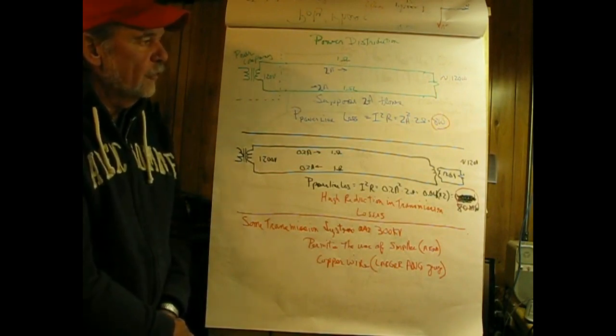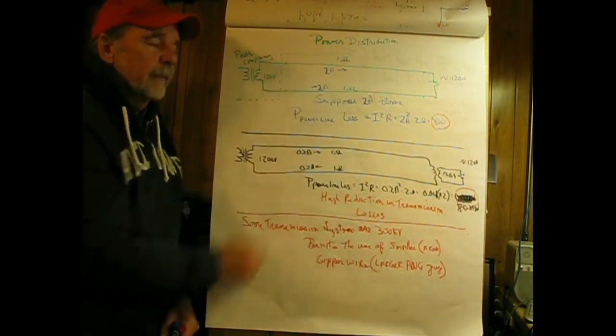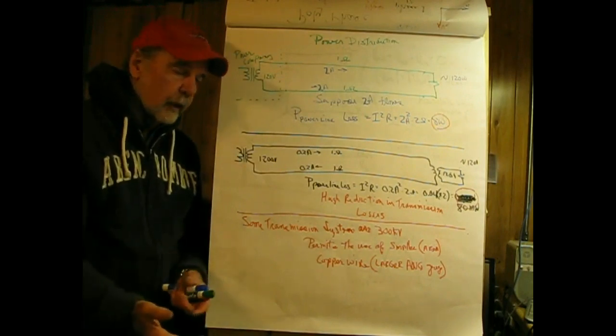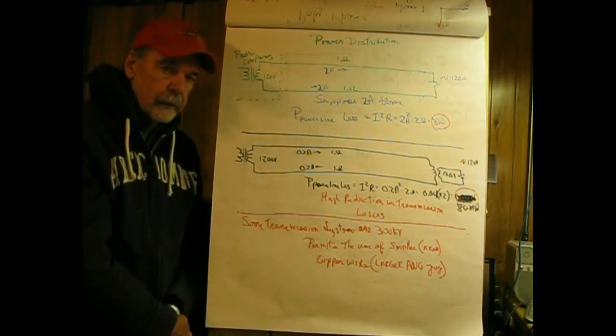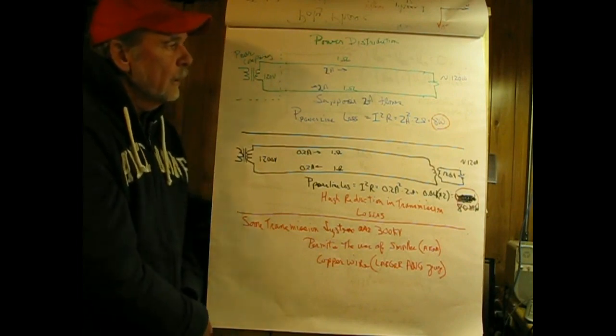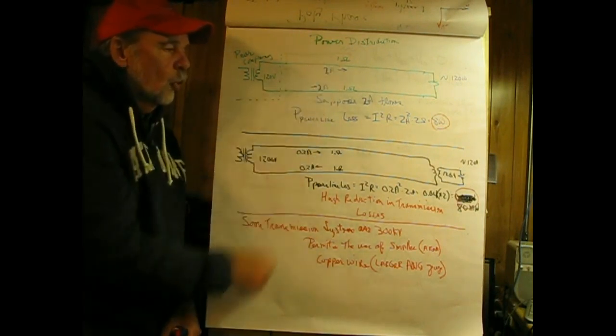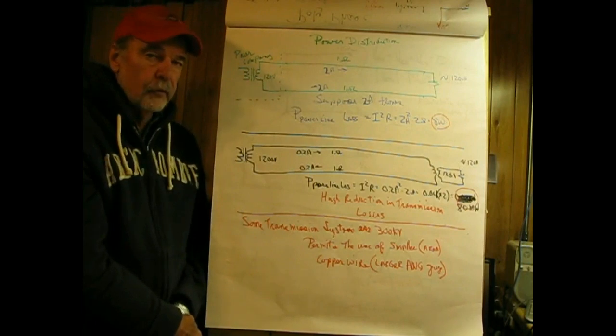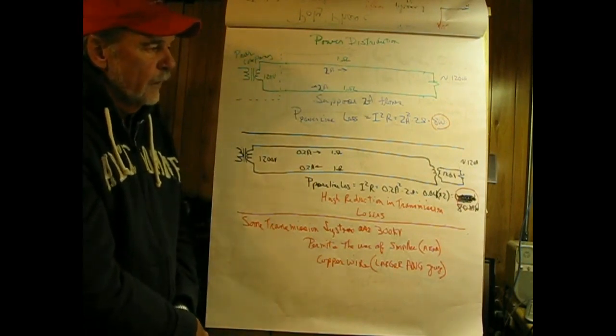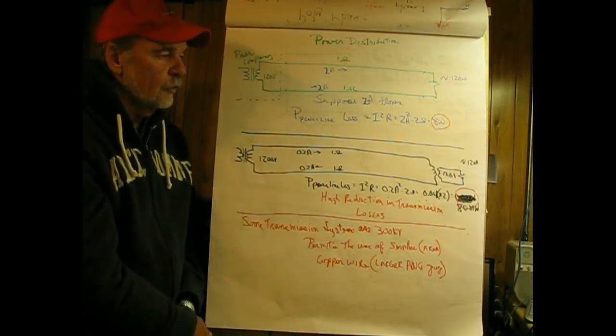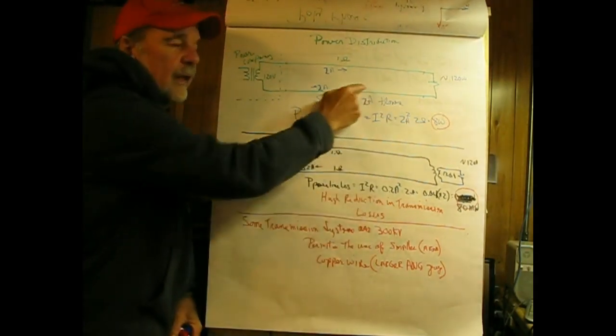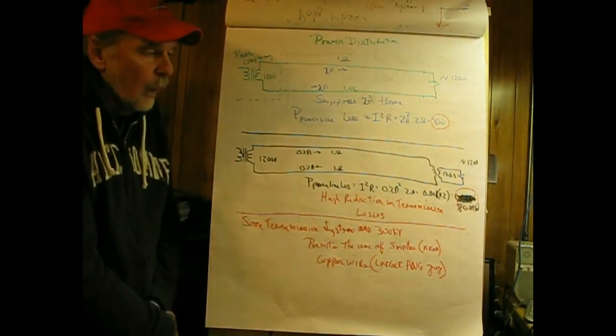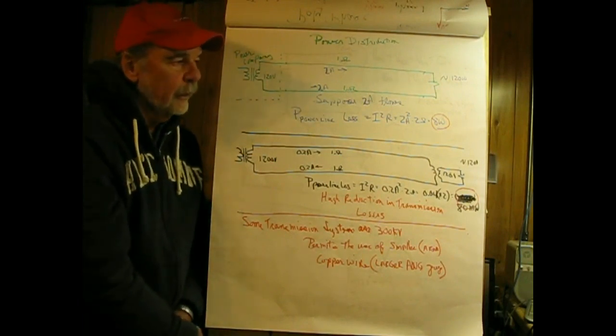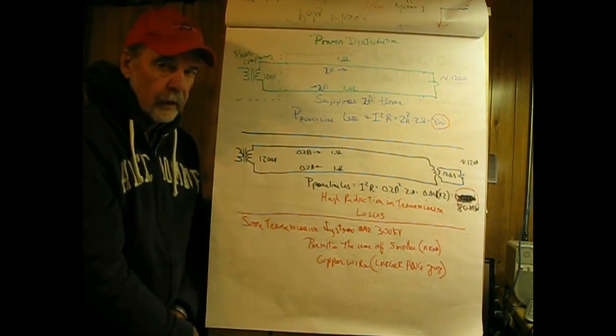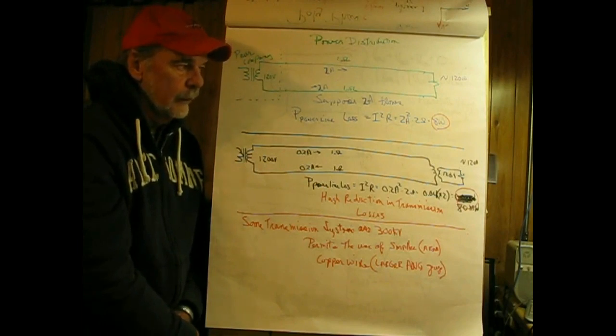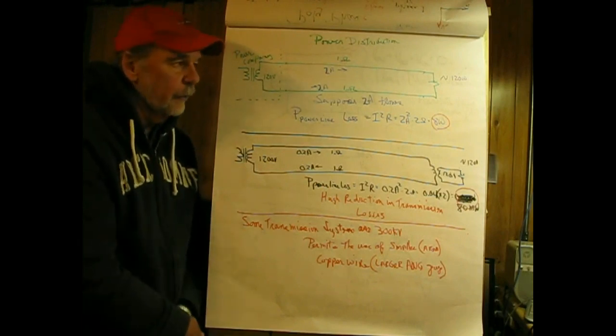And what we have is 2 amperes flowing in the circuit, and what we're going to say is that the transmission line from here to there, down the block we'll say, is 1 ohm going out and 1 ohm going back, and we're going to allow 2 amperes to flow. So if we do a little bit of math on this, what we see is the power line loss is 8 watts. Now that 8 watts is what's being lost by the electric company, and would ultimately be made up by our bills being higher.